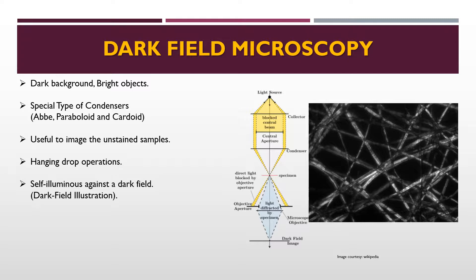In dark field microscopy, the microscope field is dark — a dark background is produced against which objects are brilliantly illuminated, like the opposite of bright field. It is used to enhance contrast in unstained samples; for example, fibers appear bright against a dark background. A special condenser transmits a hollow cone of light from the illumination source, making the object appear self-luminous against the dark field. There are three types of condensers used: Abbe condenser, paraboloid condenser, and cardioid condenser. This microscopy is particularly valuable for unstained samples and hanging drop preparations.